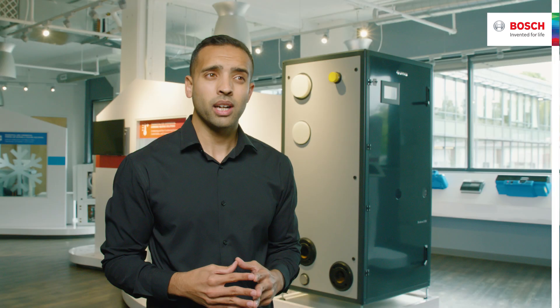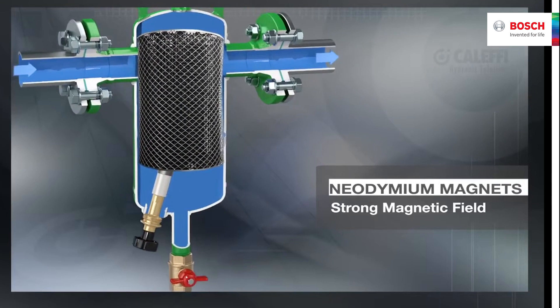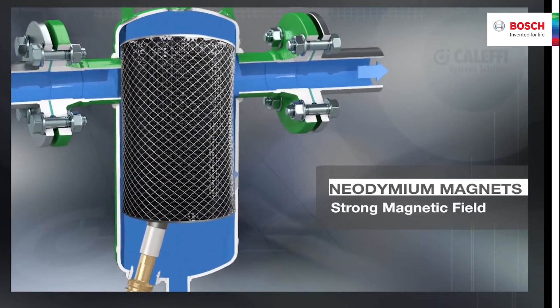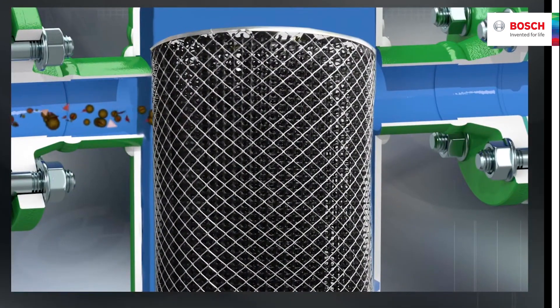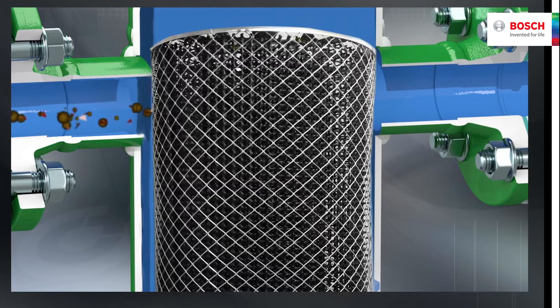The SSP Low Loss Header has two and a half times the ferrous impurities removal performance of standard air and dirt separators. We incorporate a powerful removable rare earth magnet just below the flow line to capture ferrous particles. This causes no added system pressure drop since the magnet is positioned outside the flow path.